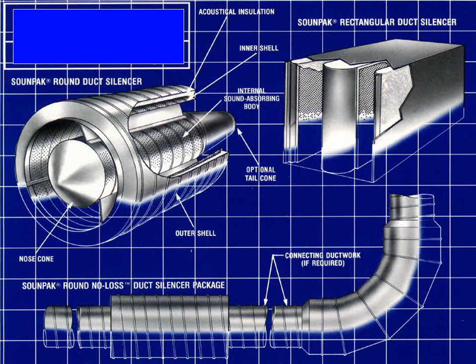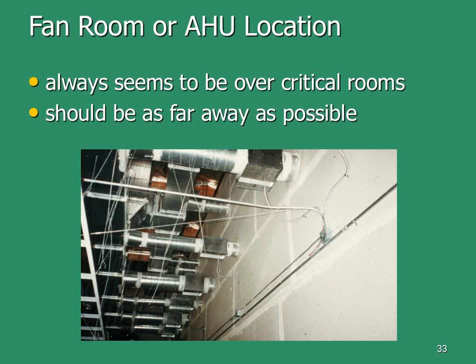If you can't use duct liner, the next step is to use a prepackaged silencer, which is basically a duct segment with baffles inside and perforations, usually filled with mineral wool or rock wool. I'll show you a picture of a rectangular version and a round version, and they work pretty well. A typical silencer might be $1,500 to $2,000, and it'll add a little pressure drop to your system — so there's a life cycle cost as well as a first purchase cost.